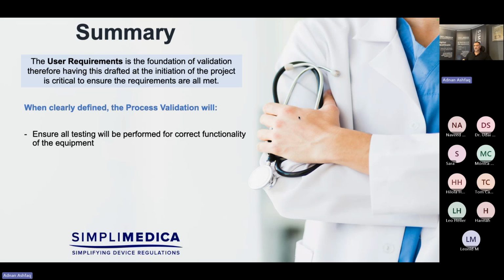So to summarize, the user requirements is really the foundation of validation, because what we're looking to do from the user requirements is that's the go-to document to understand what did we actually request at the time of manufacturing the equipment from the supplier. Now, 9 times out of 10, in my experience, when I've gone in to do validation for a process which has already been historically embedded into the manufacturing site, there is no user requirement specification.